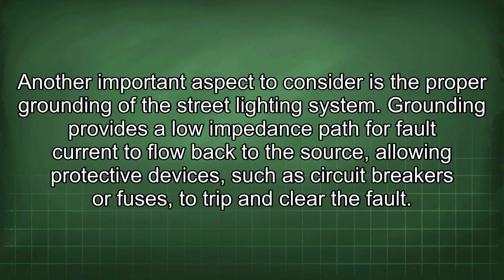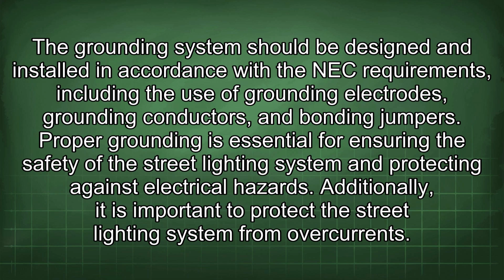Another important aspect to consider is the proper grounding of the street lighting system. Grounding provides a low impedance path for fault current to flow back to the source, allowing protective devices, such as circuit breakers or fuses, to trip and clear the fault. The grounding system should be designed and installed in accordance with the NEC requirements, including the use of grounding electrodes, grounding conductors, and bonding jumpers. Proper grounding is essential for ensuring the safety of the street lighting system and protecting against electrical hazards.